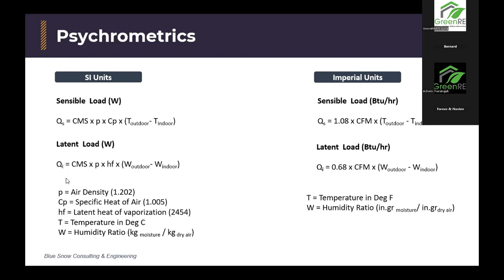So you just plug it in. This SI unit is a bit more complex because the imperial units came first, and only then the SI units came in. So you need to know the air density. I've given you the values here. This is often used for space cooling. Unless you're using it for process cooling, those values may differ because it might be going sub-zero or whatnot. But normally at 24 degrees C, the air properties are pretty much in this ballpark.